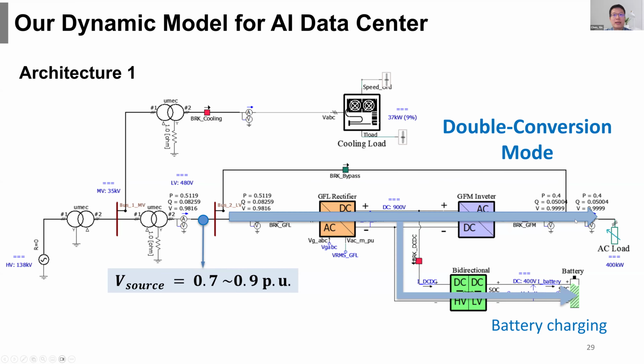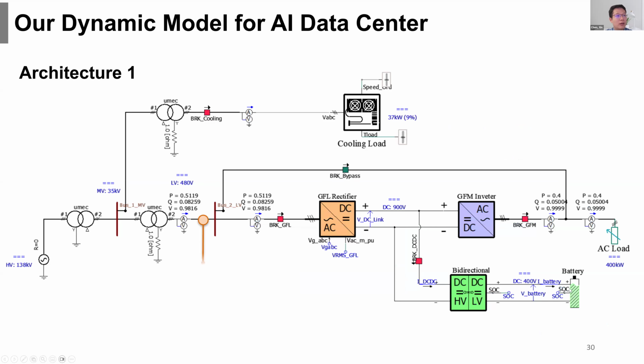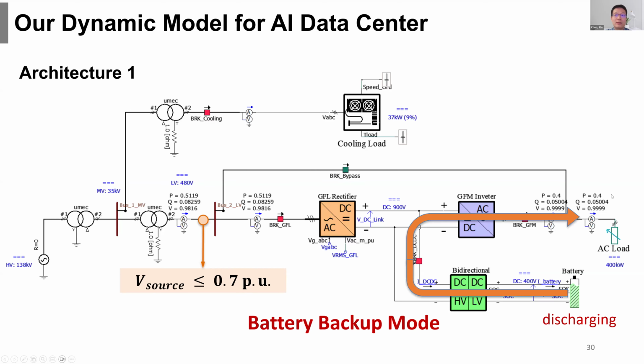Through this double conversion, we can still maintain the AC load interconnection point at a very good voltage, for example, close to 1 per unit voltage. In this case, the voltage supplied to the AC load is high quality, and also we can charge the battery if needed. And if the grid side voltage keeps dropping, for example, below 0.7 per unit, using the rectifier and inverter in double conversion, we cannot really maintain the high quality voltage on the AC load side.